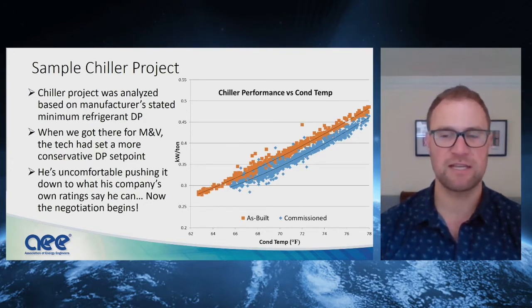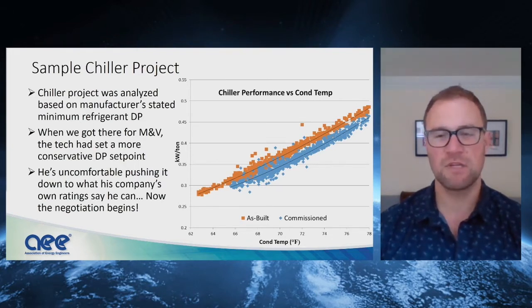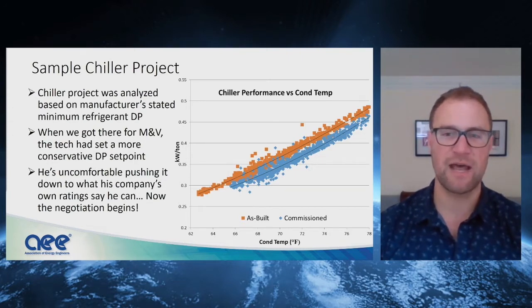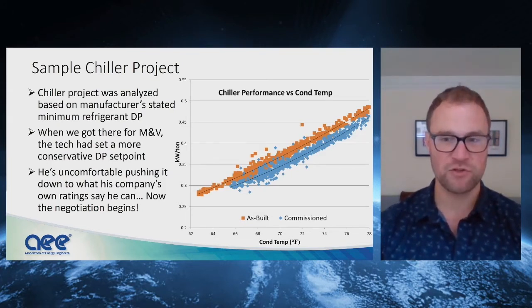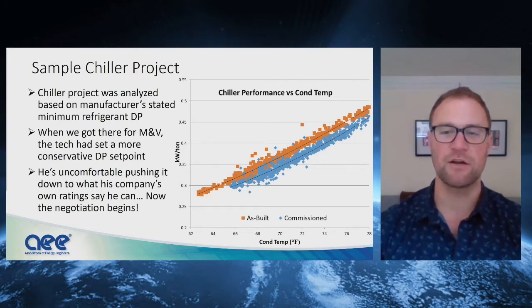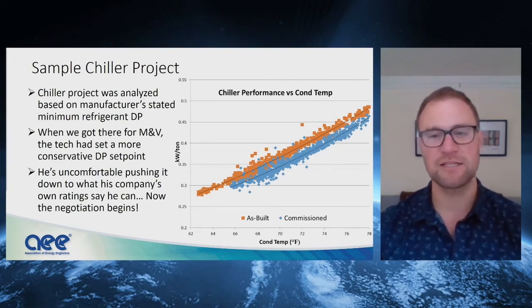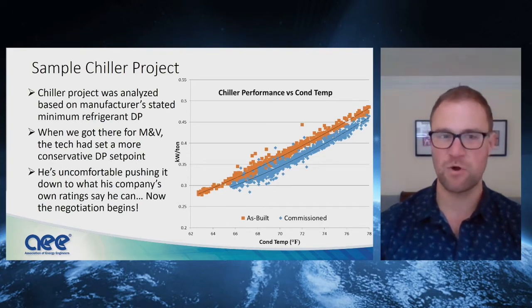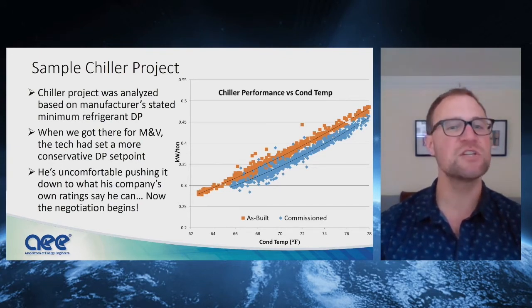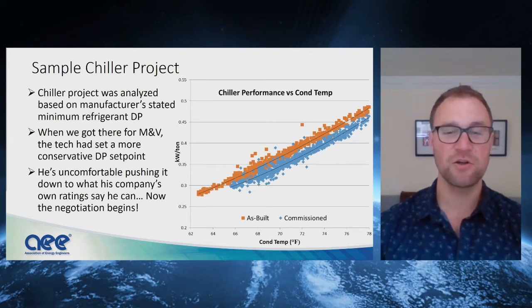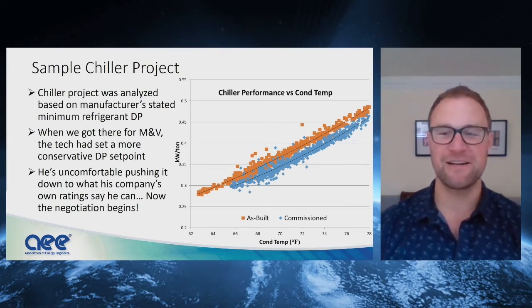So we started to challenge the tech a little bit on that. We said, what is Trane's stated minimum? He said he wasn't sure, but whatever he had set it up at, 6 or 8 PSI, was the lowest he was comfortable going. We said, well, this chiller just isn't performing per Trane's rating, so you guys need to talk to each other. He called the factory and said, okay, the factory says we can get as low as, I don't know, 1.5 or 2 PSI, but I'm just not comfortable with that, he said. So now what do you do, right? As the energy engineer, the guy is uncomfortable pushing it down to what his own company's ratings say he can.